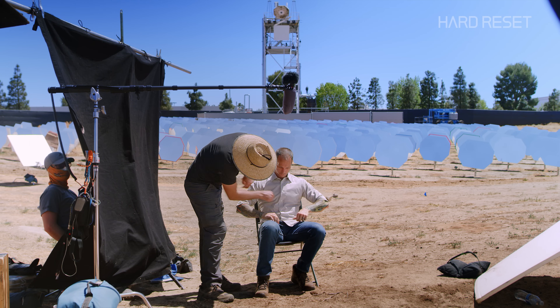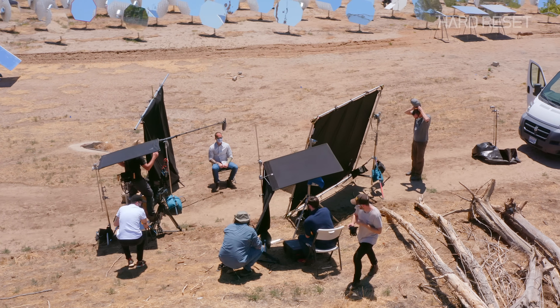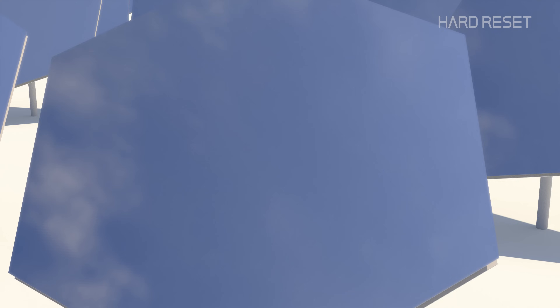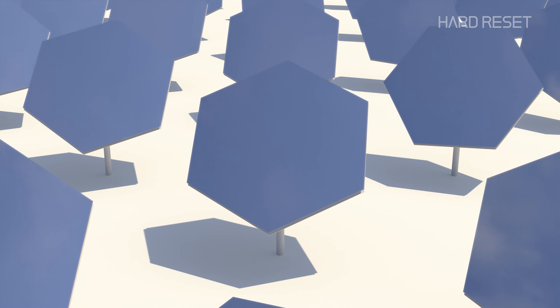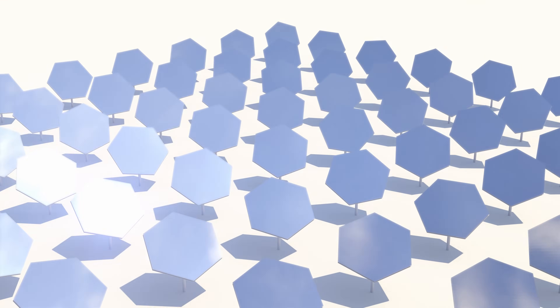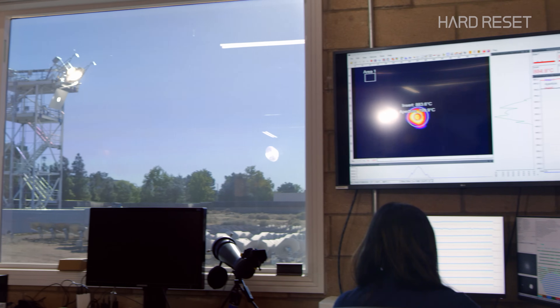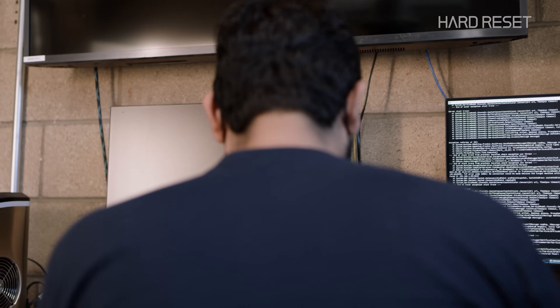Steve, who is in charge of the technology, explains: what these cameras see is a reflection of the sky close to the sun. Close to the sun, the sky appears very bright from the scattered sunlight coming through it. The further away from the sun you look, the darker that patch of sky appears to be. The AI uses that information to assess the distance from the sun, deduce the orientation of the mirror, and therefore where the beam is going. Every few seconds, we get a measurement of where that beam is going and we can command the heliostat to make small corrections. In this industry, that is a complete game-changer. Because now we don't rely on the hardware to be so precise — we have software to make it precise, which really changes everything about how that plant operates and allows us to reach higher performance levels at a much lower cost.